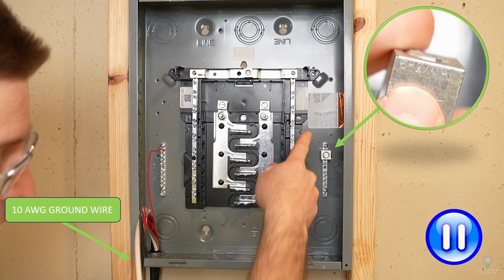There is absolutely no reason that we couldn't come around like this and land on this ground bar over here. That would be totally acceptable because both of these ground bars are electrically connected together because they both screw into the case of the panel. So they're connected together. So it doesn't matter if we tie to the left bus bar or the right bus bar for the ground.